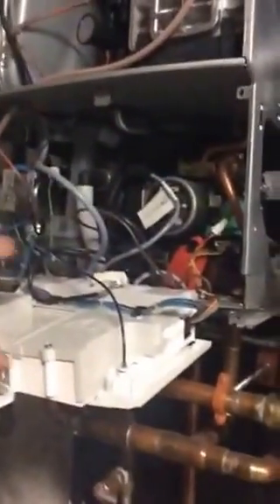The biggest piece of this is obviously having the boiler turned off, and once you start your pump and begin flow through the unit, the boiler has to be actually turned on for the initial minute or so so the domestic side can open up with the diverter valve. Once it's opened, you can pull the plug, keeping that valve in place and circulating through that flat plate heat exchanger.